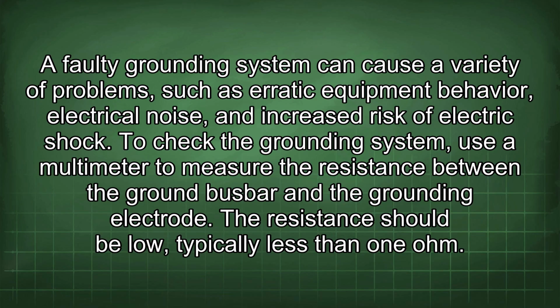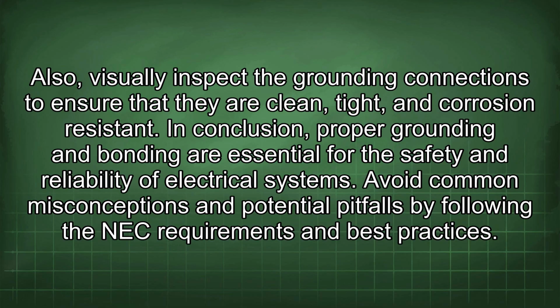A faulty grounding system can cause a variety of problems such as erratic equipment behavior, electrical noise, and increased risk of electric shock. To check the grounding system, use a multimeter to measure the resistance between the ground busbar and the grounding electrode. The resistance should be low, typically less than 1 ohm. Also, visually inspect the grounding connections to ensure that they are clean, tight, and corrosion resistant.